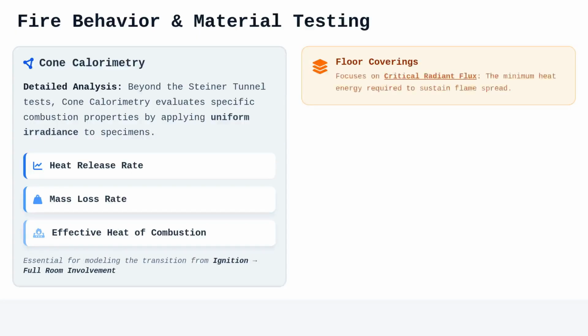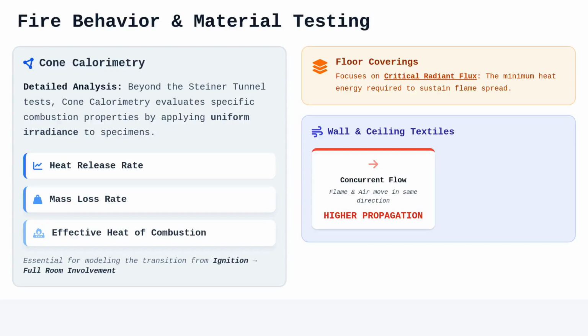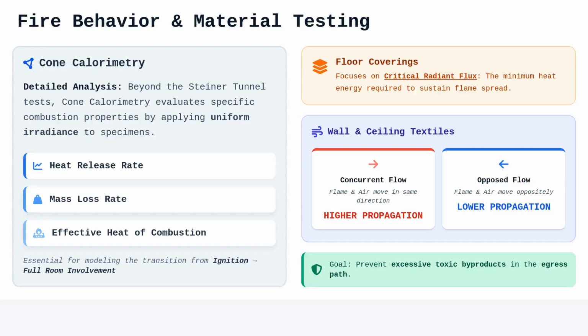In floor coverings, the regulatory focus shifts to critical radiant flux, which measures the minimum incident radiant heat energy required to sustain flame spread. Textiles and finishings along walls and ceilings behave differently because they are subject to both concurrent and opposed flow flame spread. Concurrent flow spread, where the flame progresses in the same direction as the airflow, generally results in significantly higher propagation rates than opposed flow. Recognizing these nuances helps in selecting materials that do not exacerbate the spread of fire or introduce excessive toxic combustion byproducts into the egress path.